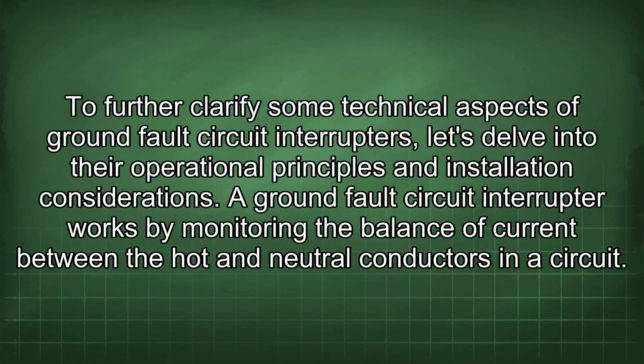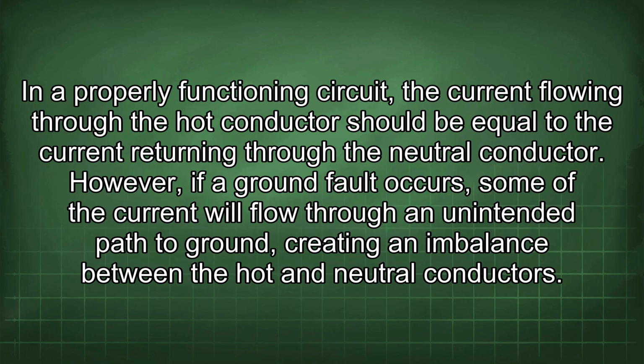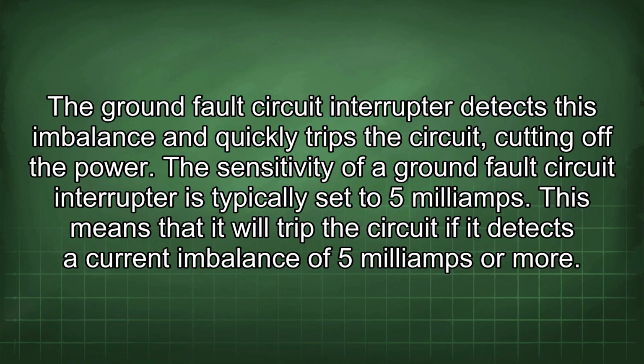To further clarify some technical aspects of ground fault circuit interrupters, let's delve into their operational principles and installation considerations. A ground fault circuit interrupter works by monitoring the balance of current between the hot and neutral conductors in a circuit. In a properly functioning circuit, the current flowing through the hot conductor should be equal to the current returning through the neutral conductor. However, if a ground fault occurs, some of the current will flow through an unintended path to ground, creating an imbalance between the hot and neutral conductors. The ground fault circuit interrupter detects this imbalance and quickly trips the circuit, cutting off the power.